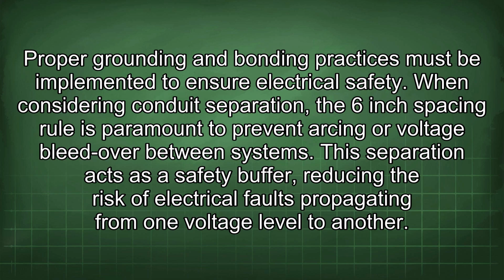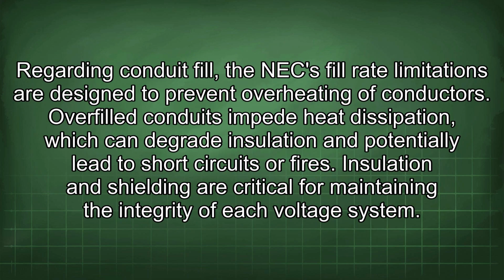When considering conduit separation, the 6-inch spacing rule is paramount to prevent arcing or voltage bleed over between systems. This separation acts as a safety buffer, reducing the risk of electrical faults propagating from one voltage level to another. Regarding conduit fill, the NEC fill rate limitations are designed to prevent overheating of conductors. Overfilled conduits impede heat dissipation, which can degrade insulation and potentially lead to short circuits or fires.